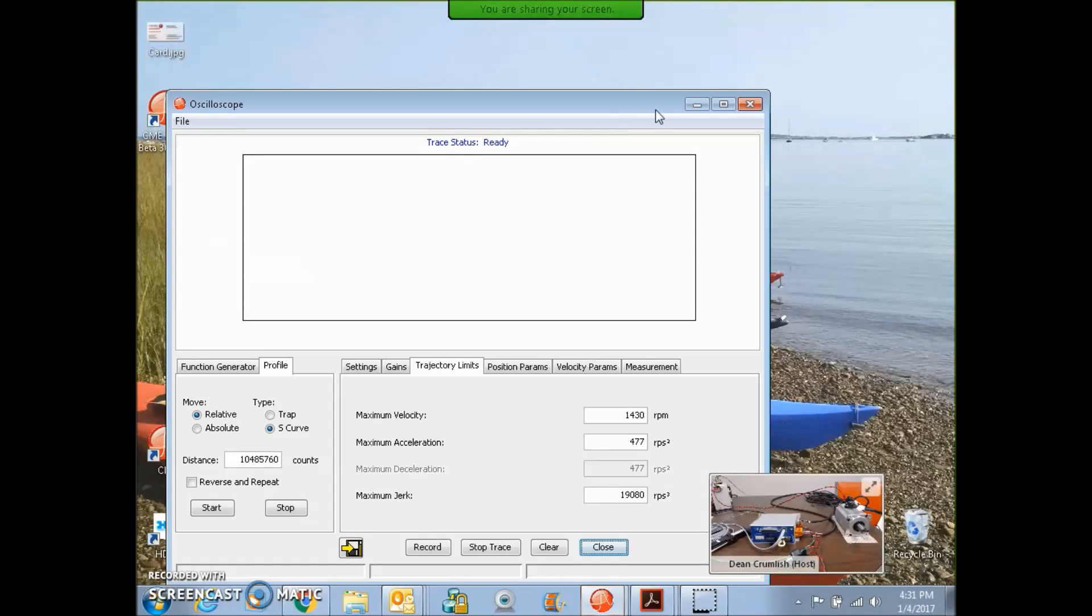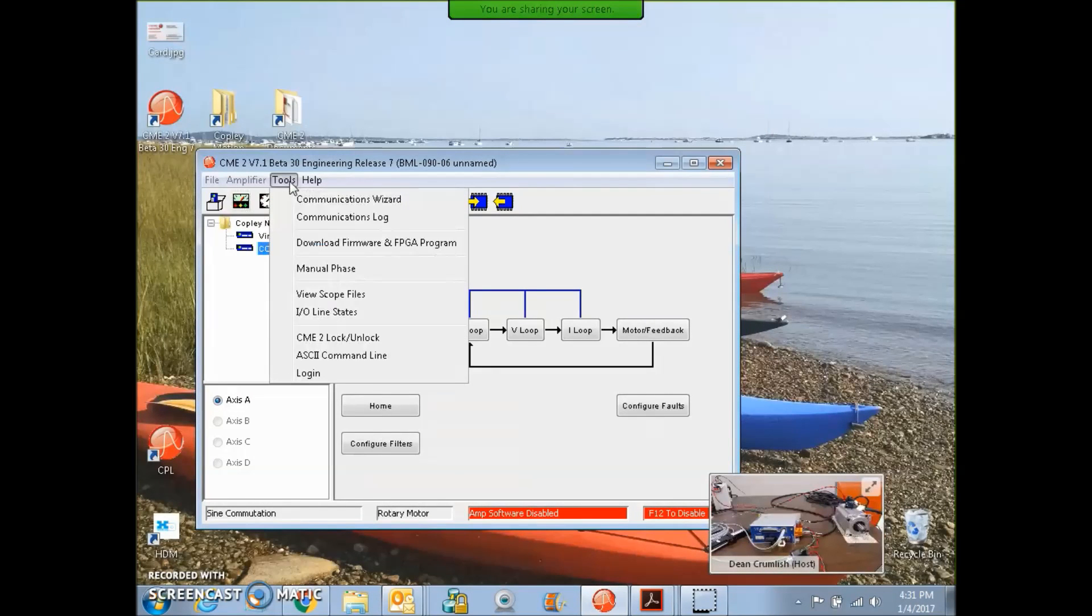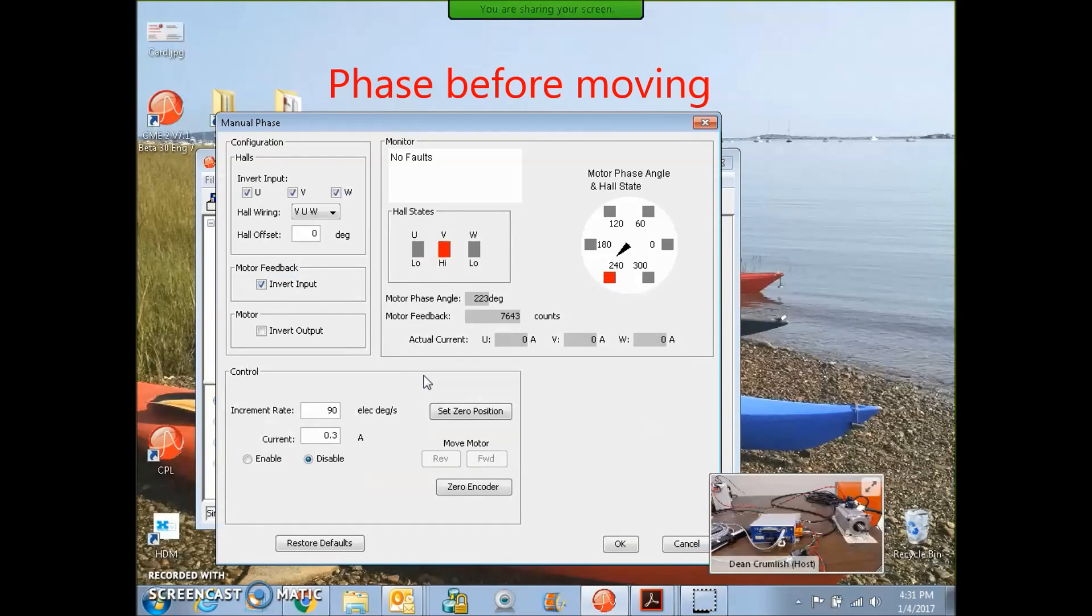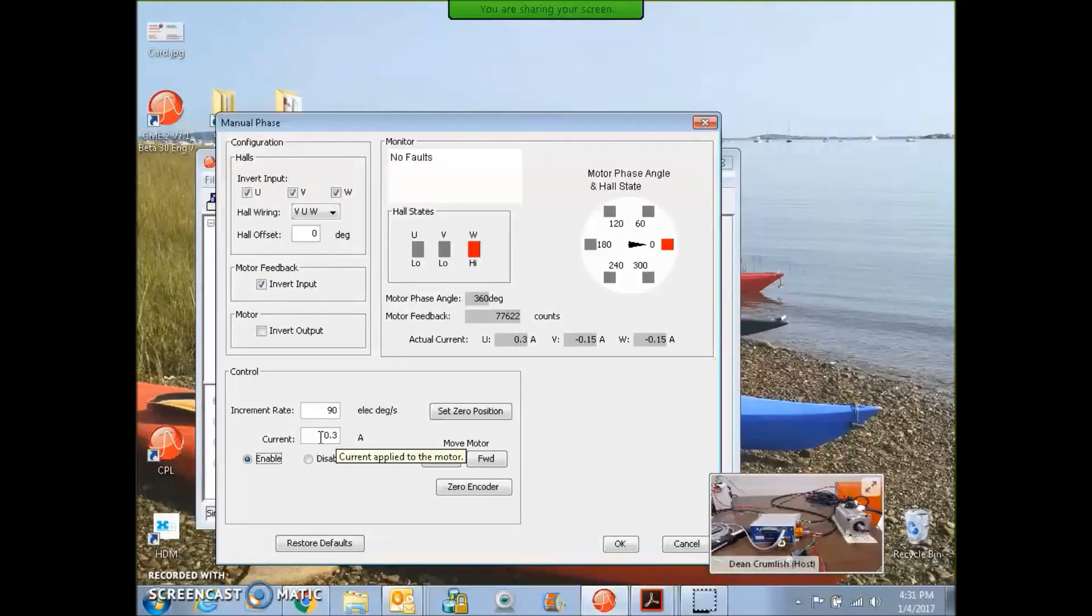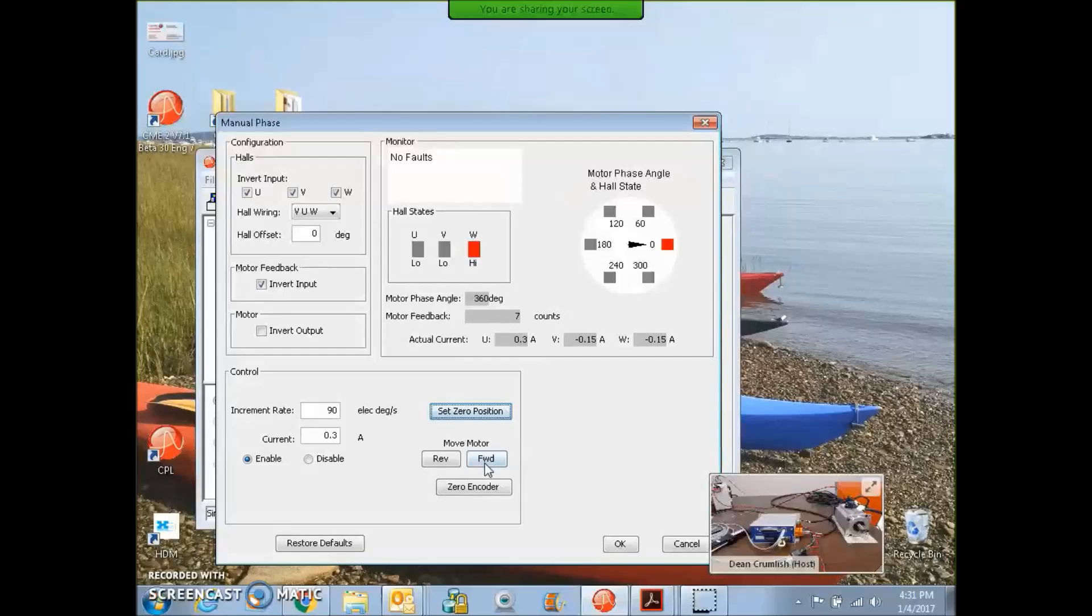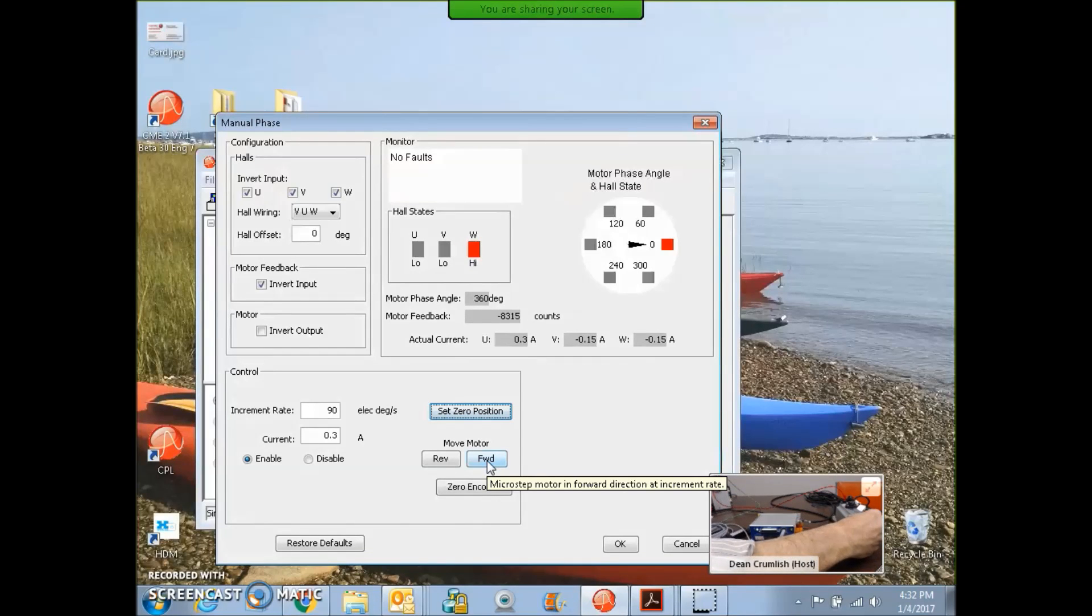Before I do the tuning, we should take a look at the manual phasing. In the control section, you can enable the current vector. This is 10% of the rated current, and we can set the zero position to start at zero, and we can rotate the motor shaft with the current vector. Right now, it's pointed that way.